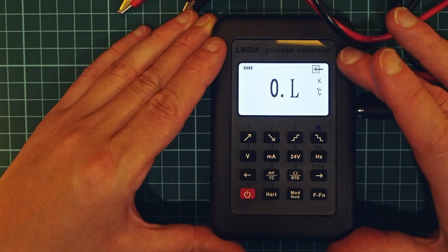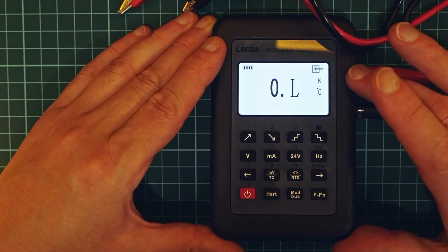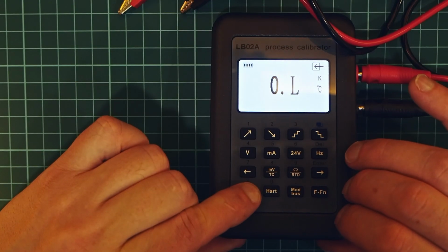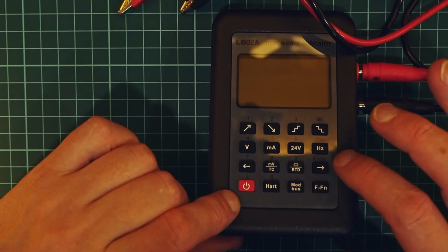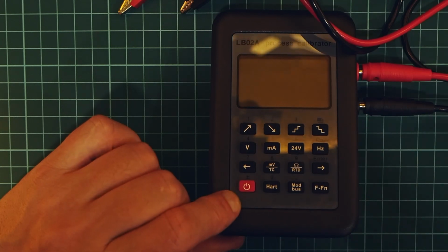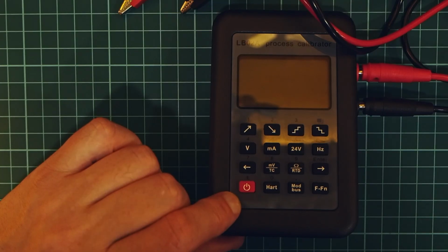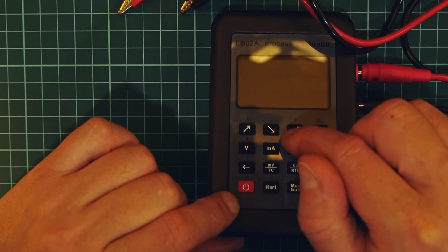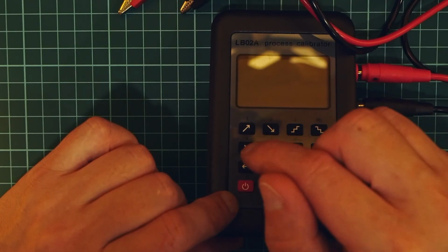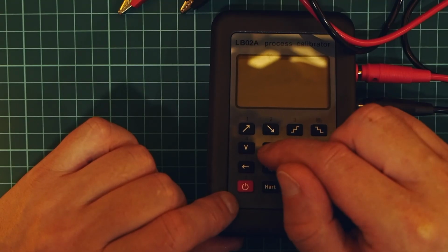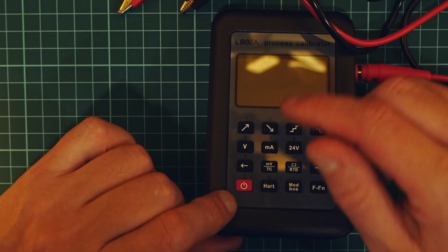In the measuring side where you actually want to measure thermocouples, what I suggest is to turn it off and leave it there for 2 hours. It will be the same temperature as the ambient temperature. Then you measure the ambient temperature with another measuring device, and you enter this value here in manual cold junction. So it will be a reference point, and you will have a more precise measurement.